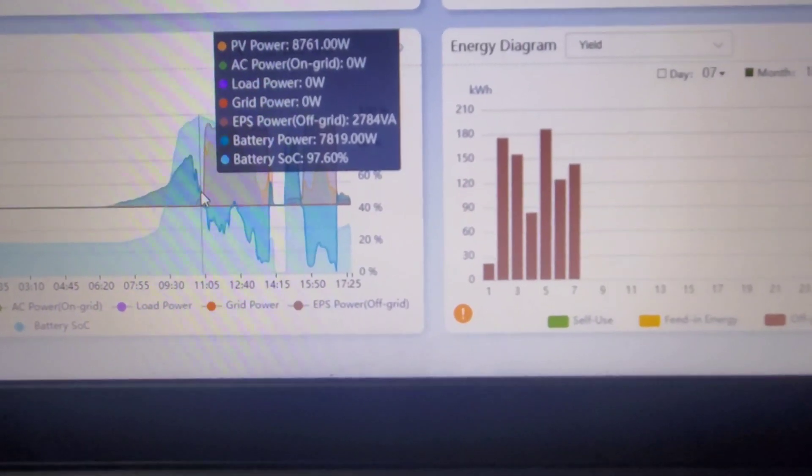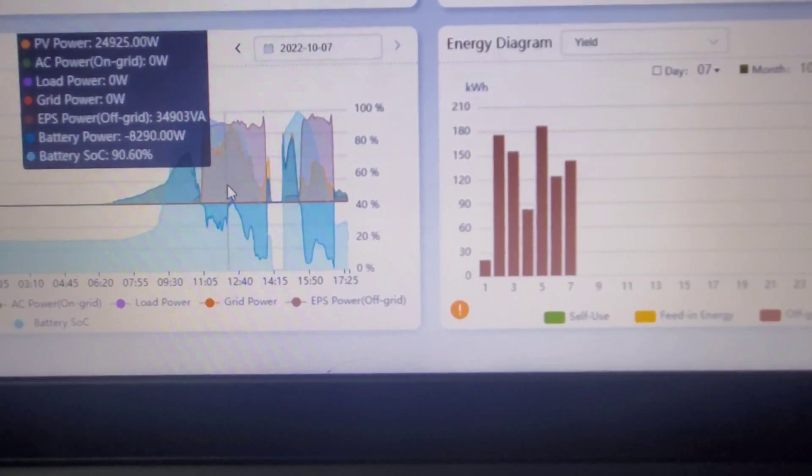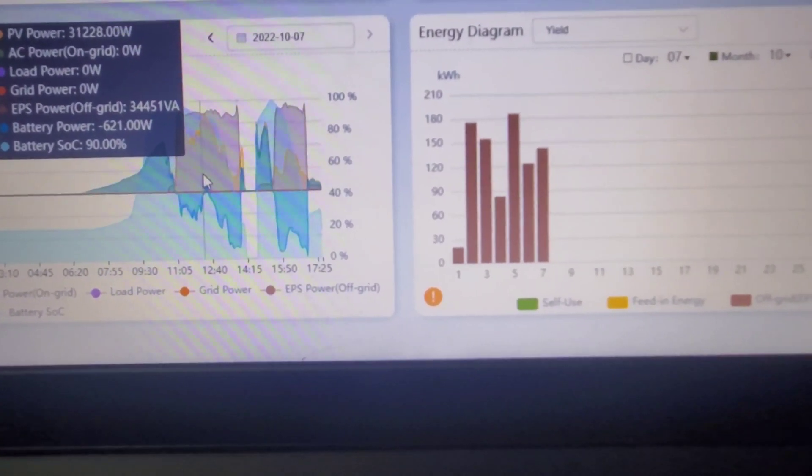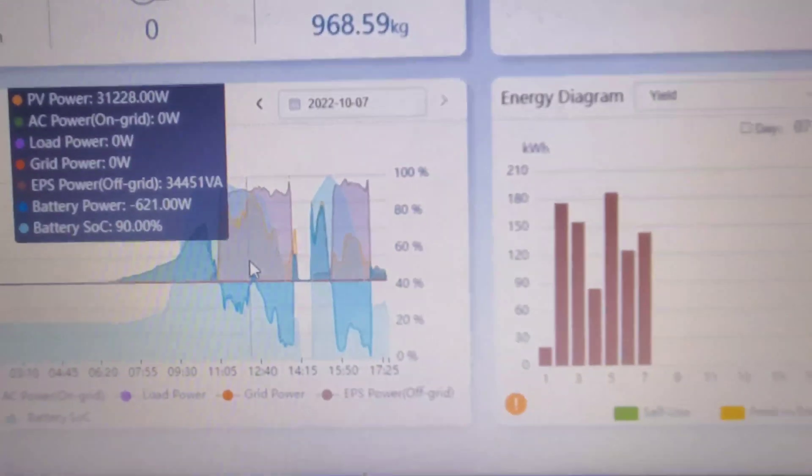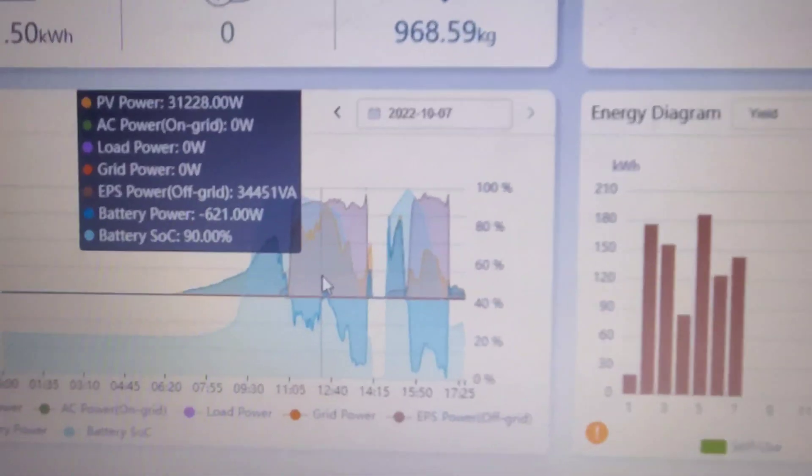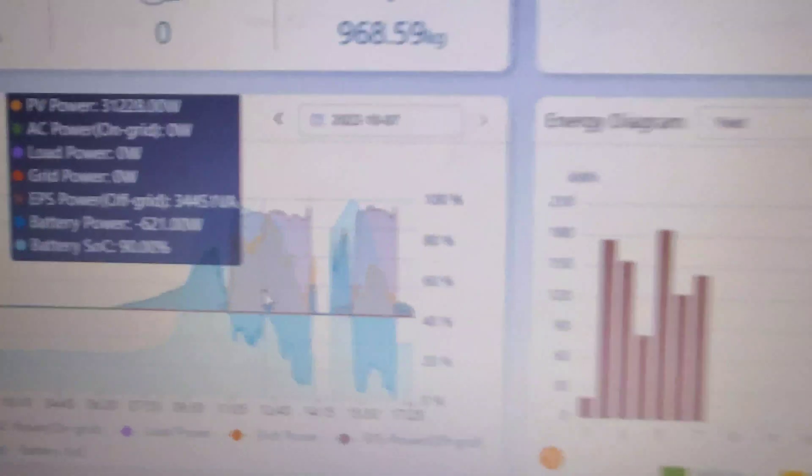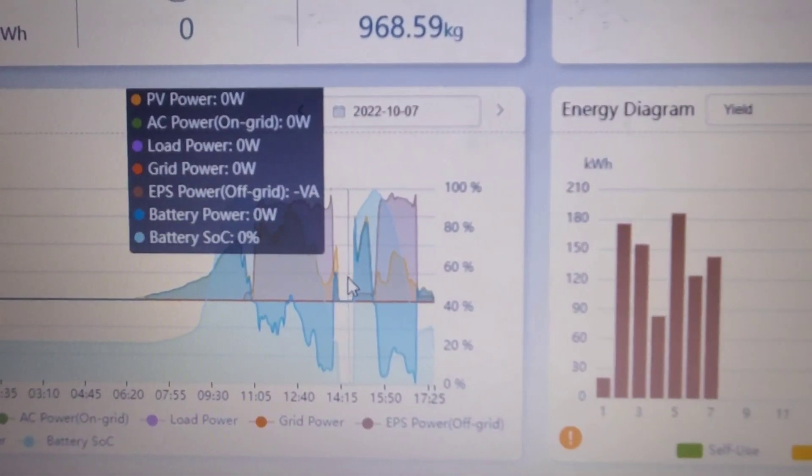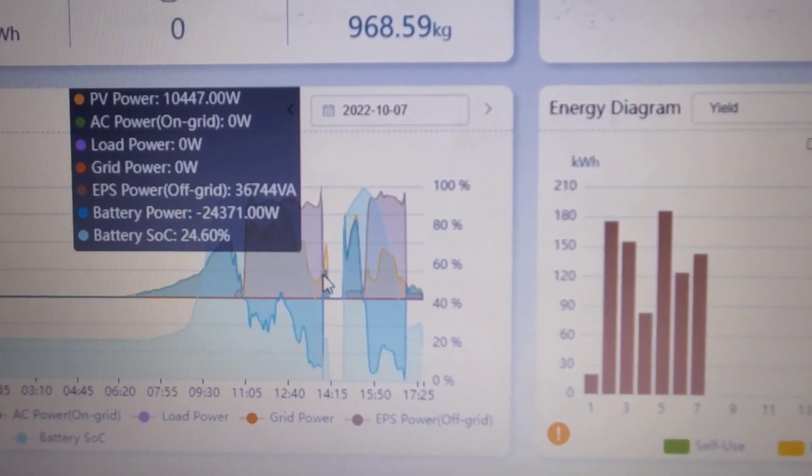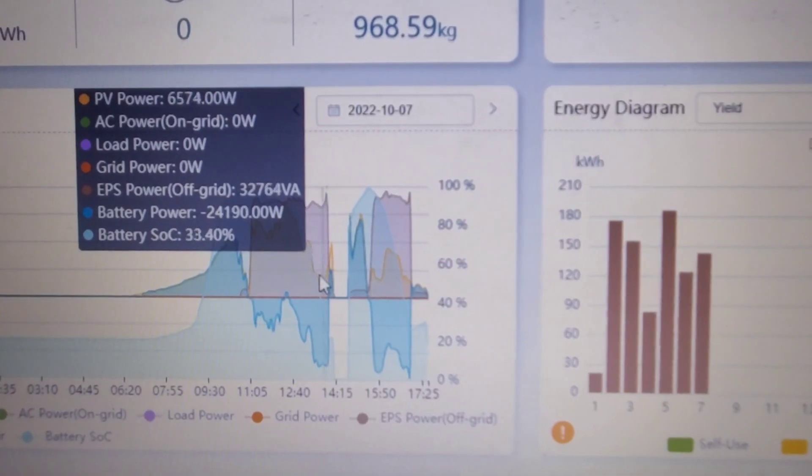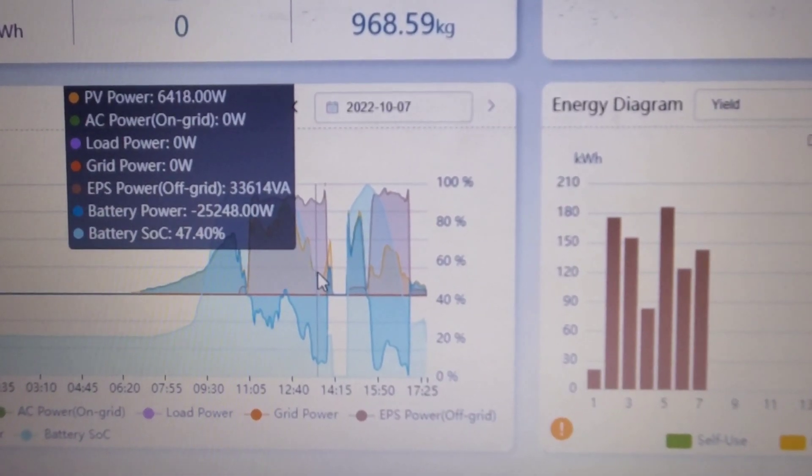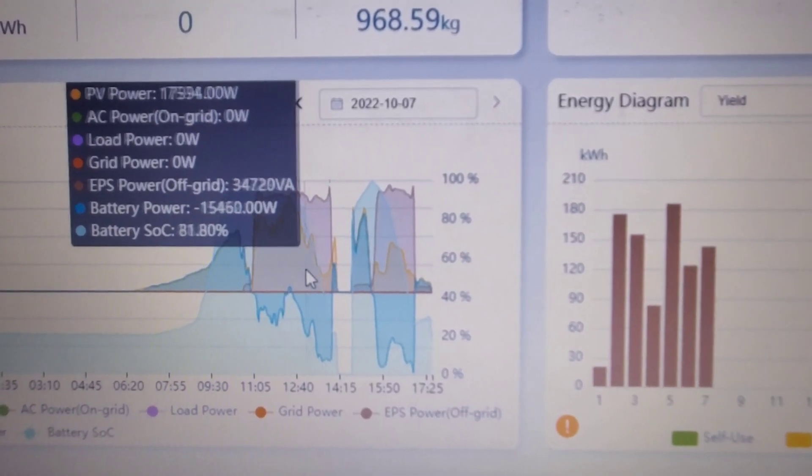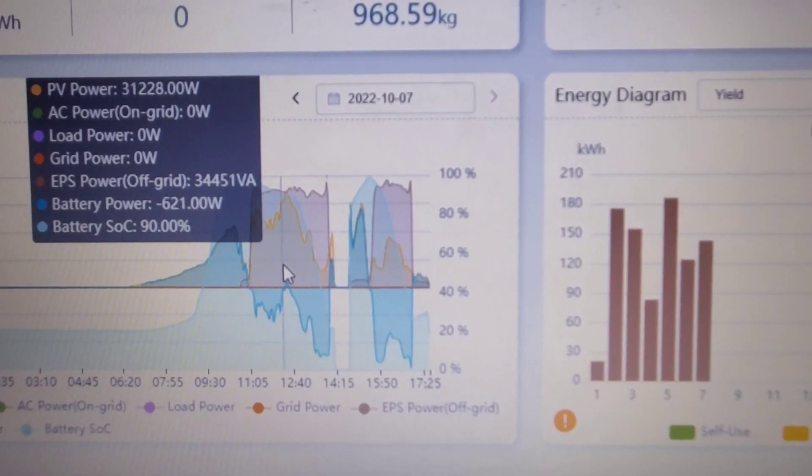Here we were at EPS power—we're pulling 34 kilowatts and the panels were producing 31 kilowatts. Then here we turn off because our batteries, as you can see, had this fictitious reading. We went from very high numbers to ridiculously low numbers in a very short time period.